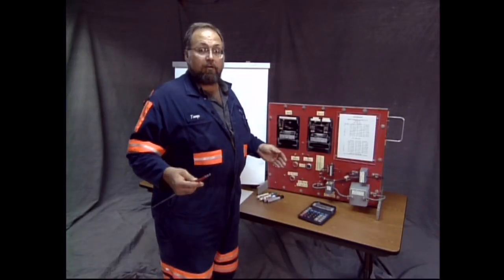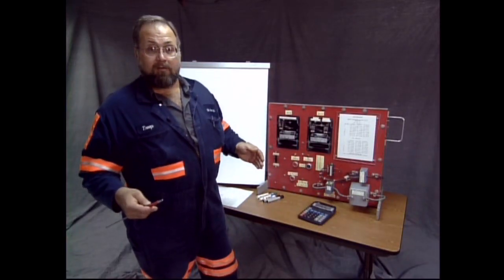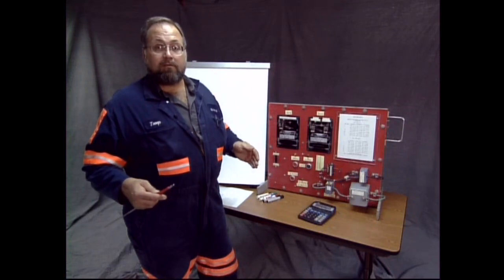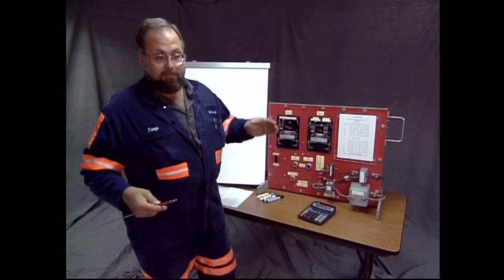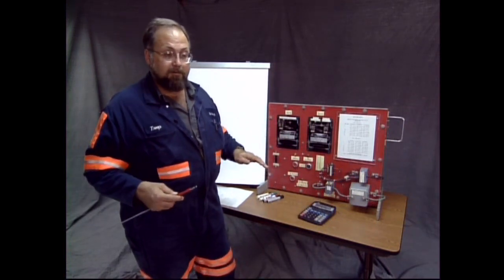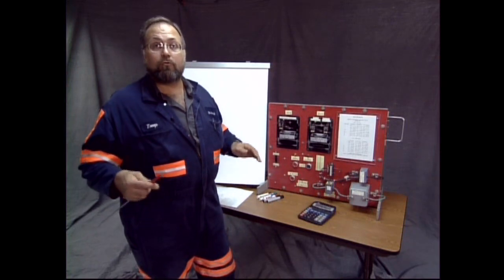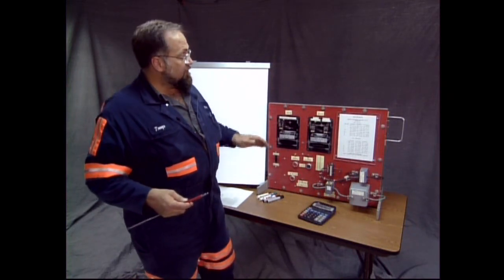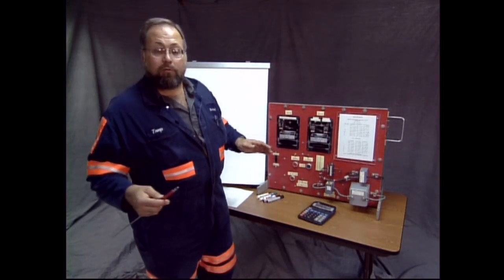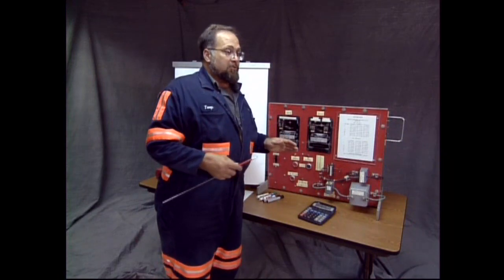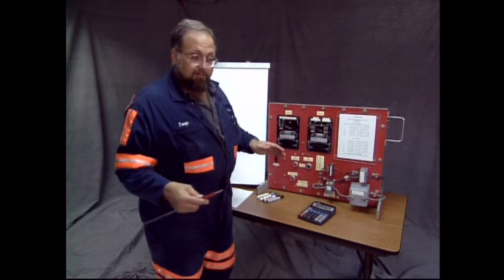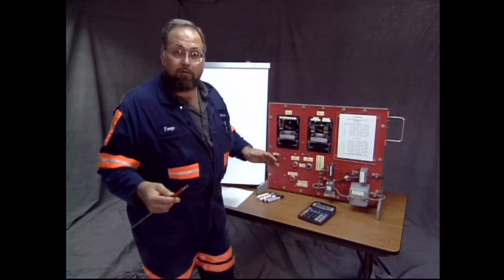An oil circuit breaker is in an oil bath. And if the reservoir is leaking, then the part that suppresses the flash and insulates this breaker is leaking out. You're going to look for a leak. A visual examination: broken, missing parts, thermal damage, a leak, anything that's out of the ordinary, that's wrong.